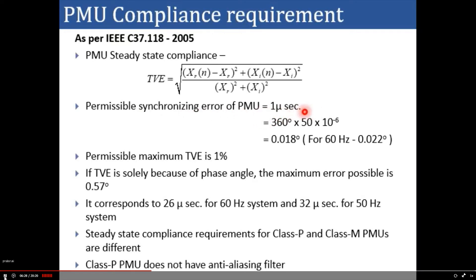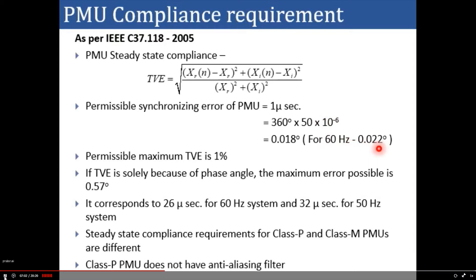The permissible synchronizing error in PMU is 1 microsecond — that is, the PMU clock synchronized with a 1 PPS signal has a maximum delay of 1 microsecond. Translating this to an angle value: 360° × 50 × 10^-6 = 0.018° for a 50 Hz system. Replacing 50 by 60 Hz gives a maximum synchronizing error of 0.022°.